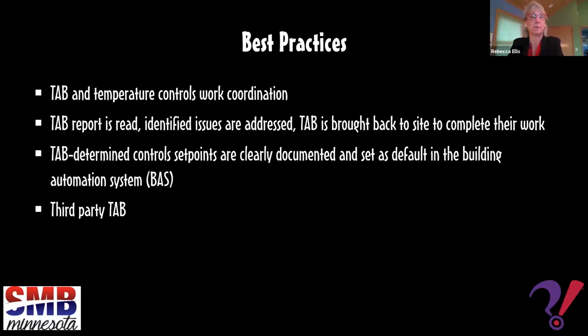Controls are critical for making sure the systems perform as required. TAB needs controls to manipulate the systems as part of the balancing process, and controls need TAB to understand what the correct set points are for control sequences. And TAB and controls are often a tag team effort. Controls need to be complete to a certain extent before TAB can be performed, and then controls cannot be completed until TAB is complete and the control system set points determined. So it's not as simple as saying you've got to finish controls and then you have to do TAB. It's an iterative process between the two of them. And the sooner those two subcontractors start talking to each other, the better the process will be.